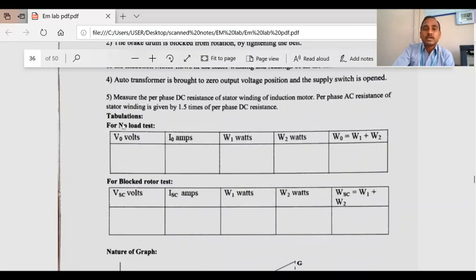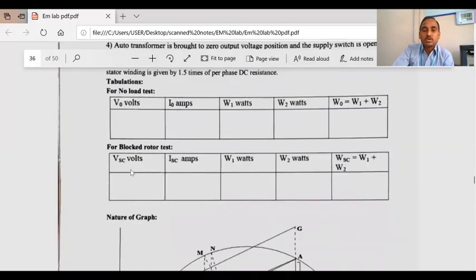Okay, then a tabulation for no load test. You take V naught, I naught, and W naught readings. If you are using the 2 wattmeter method, note down W1 and W2 values and sum them. If you are using only the multifunction meter, you can directly take V naught, I naught, and W naught values. And for the blocked rotor test, that is VSC, ISC, and WSC. Those readings can be noted down.